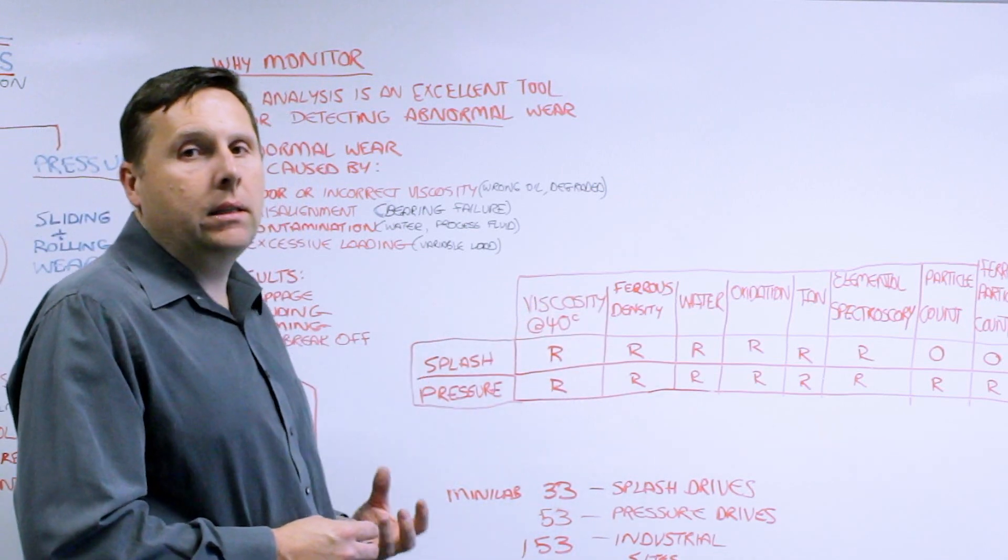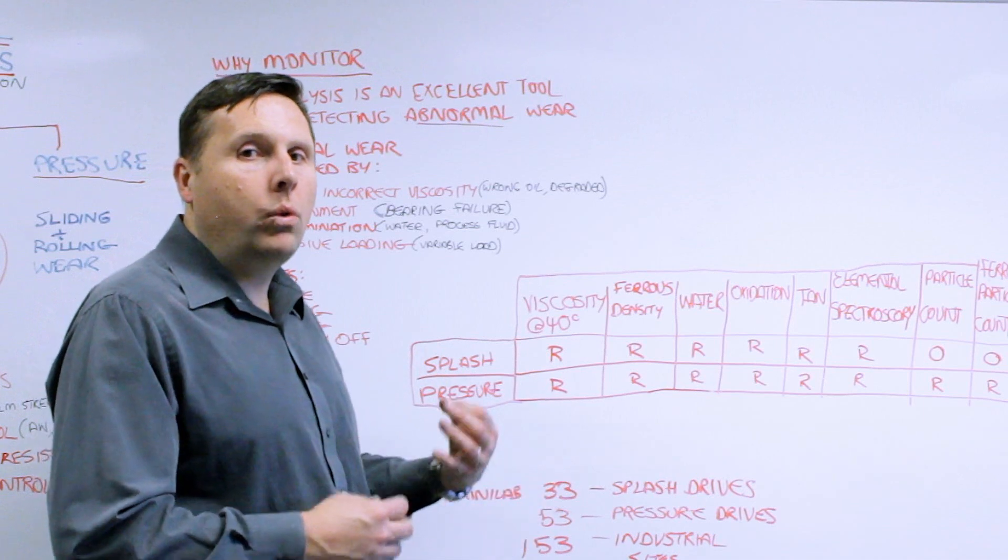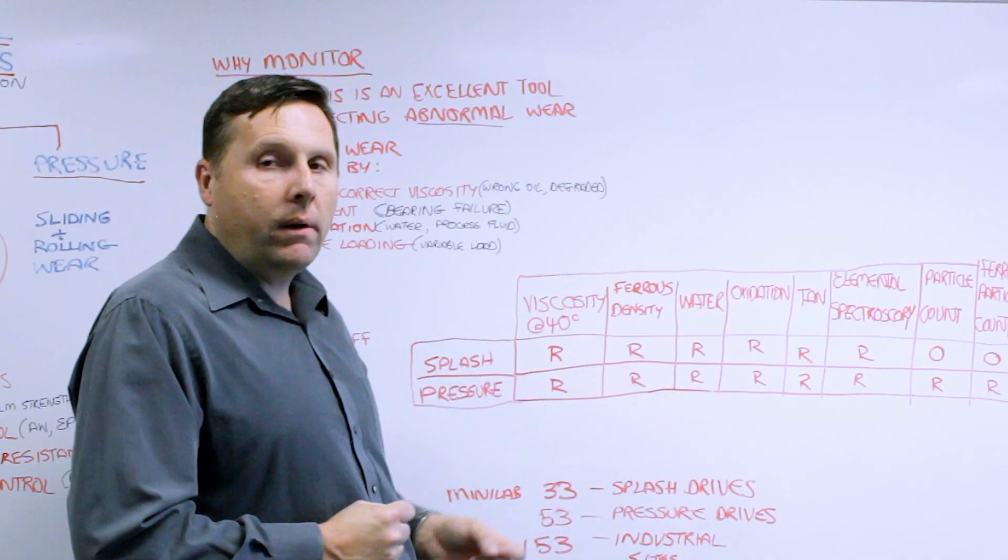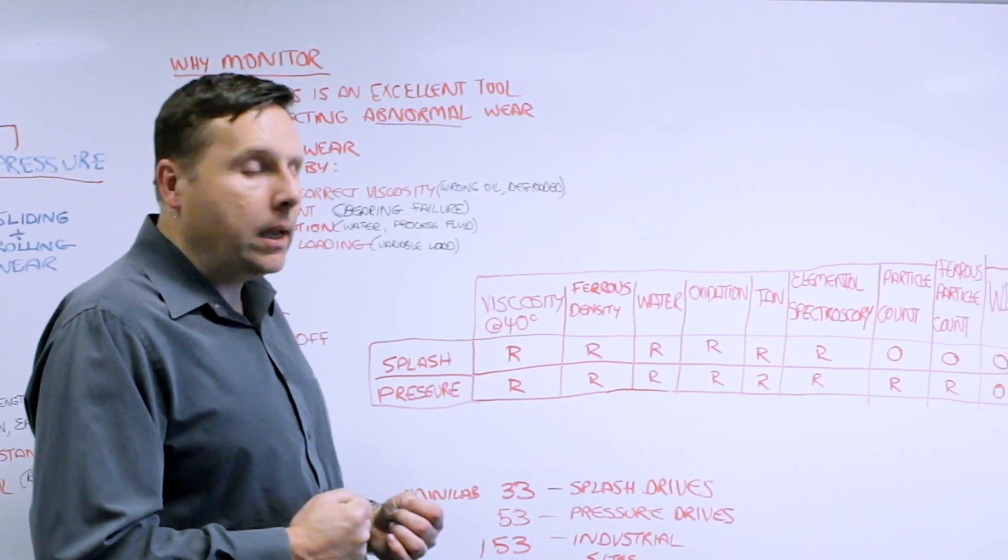Ferrous density is an excellent screening tool for the large abnormal ferrous wear that can occur when you have abnormal wear being produced. You want to check for water contamination. It's the most common liquid contaminant getting into the system.